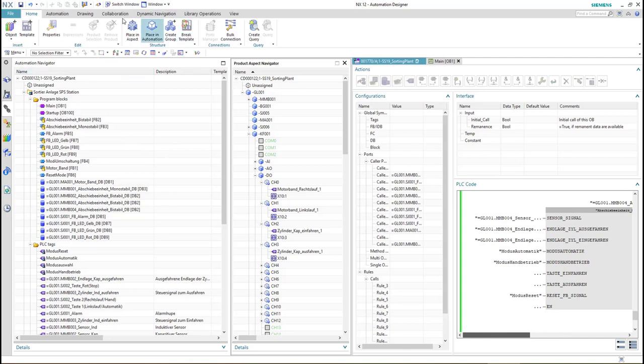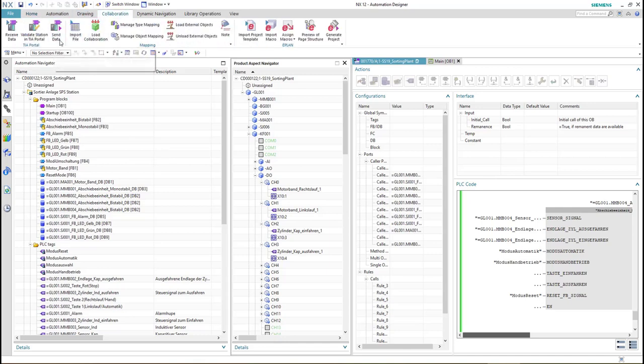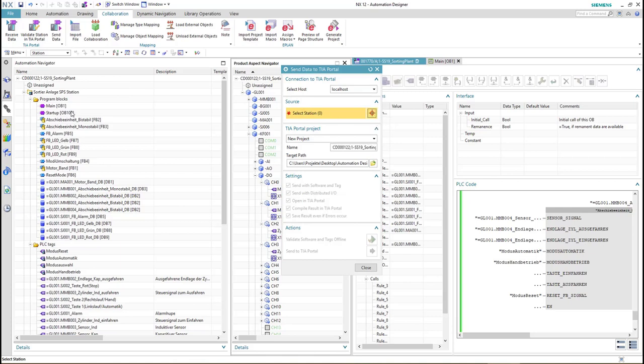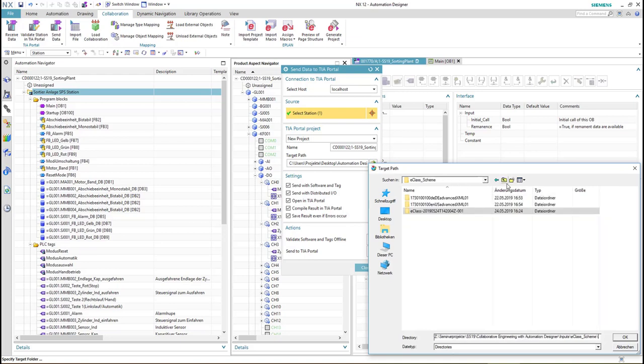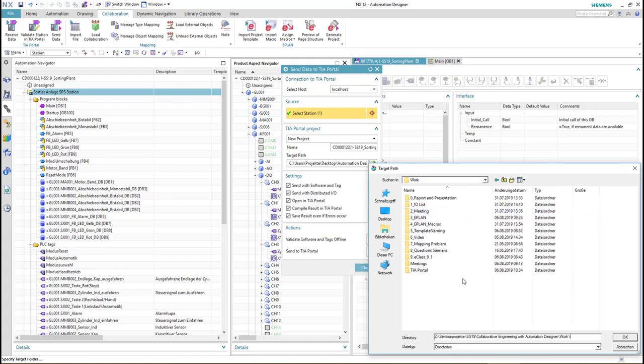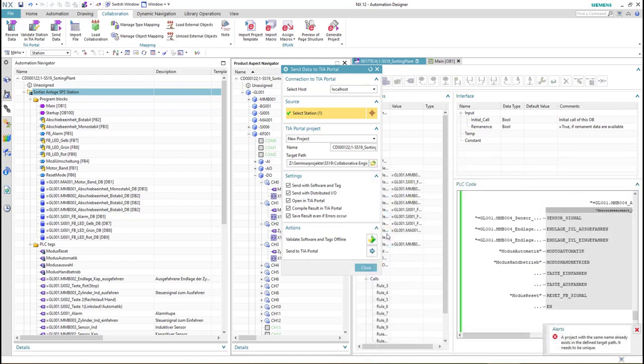Afterwards we are able to generate the PLC code — the TIA portal project — from collaboration, then send data. From the source we select our system, select new project, specify the name and target path. We configure the options such as compiling the results in TIA portal, opening TIA portal itself, and sending the software and tags. Then we click send to TIA portal.